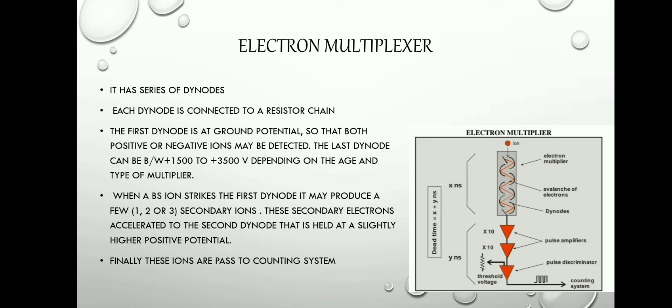First, about the electron multiplexer. It has a series of dynodes. Each dynode is connected to a resistor chain. As you can see in the diagram, the first dynode is at ground potential so that both positive or negative ions may be detected. The last dynode can be between +1500V to +3500V depending on the age and type of multiplier.